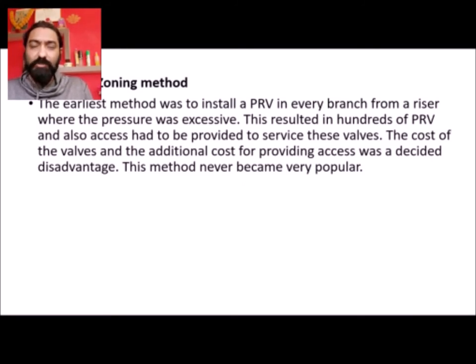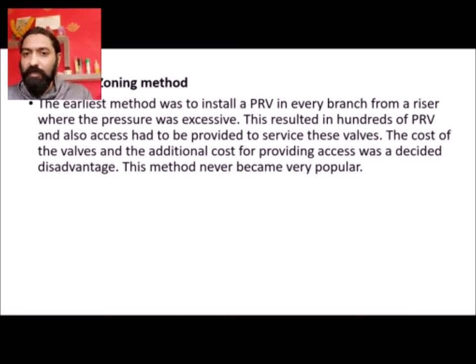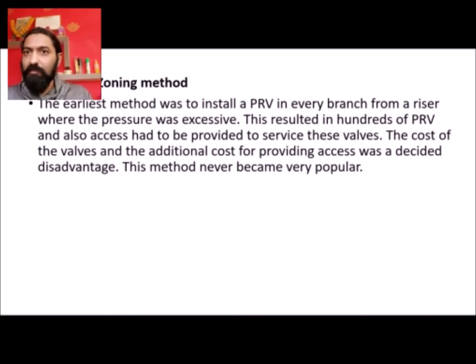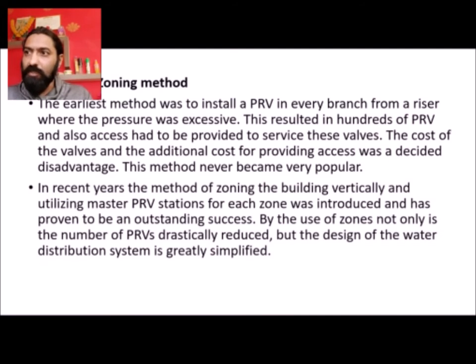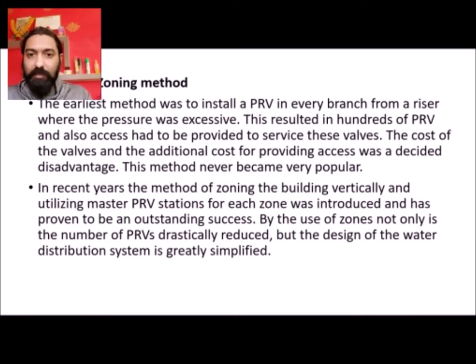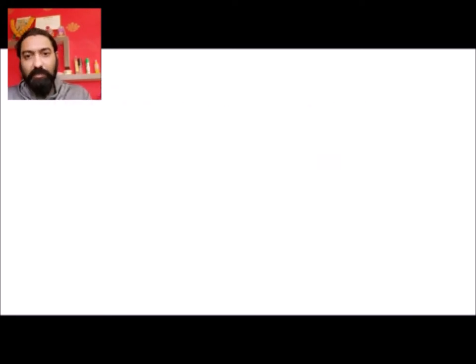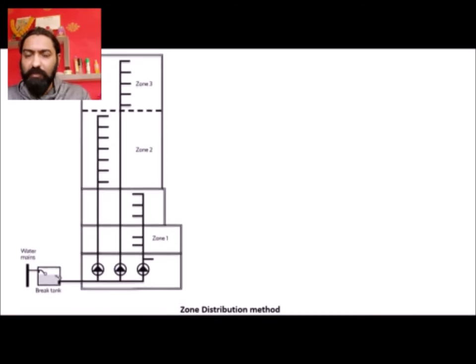In such cases, we can use pressure reducing valves (PRV) and a technique called zoning. Depending on the various designs of the building, there may be mechanical or plumbing rooms at different levels, each with a pressure tank, to regulate the water supply pressure. Instead of a single water storage tank at roof level, we can split it into multiple smaller portions at various parts of the building.